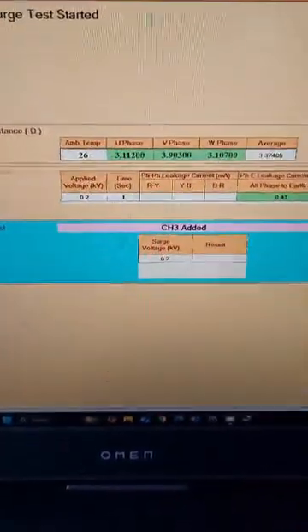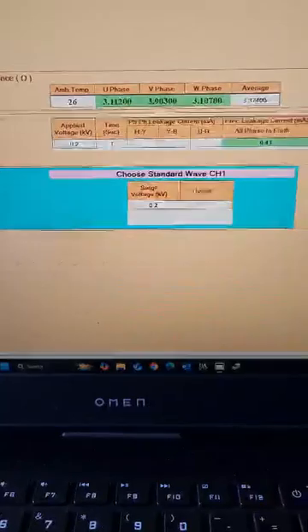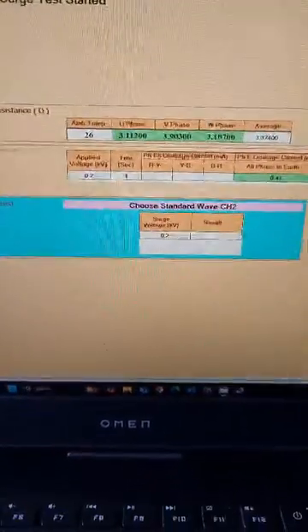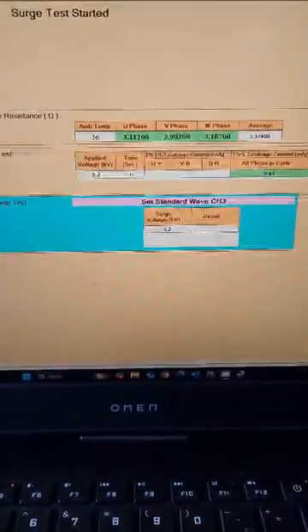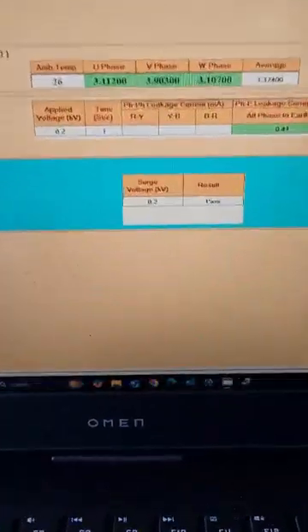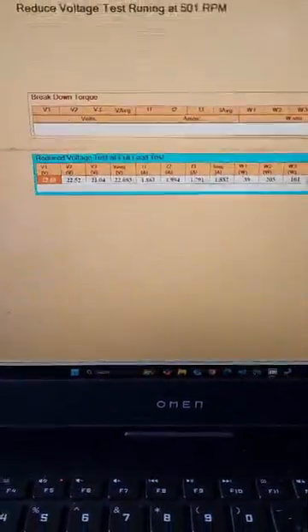And the meter that we have for the surge testing, whatever message is displayed on that particular screen of the meter is also captured on this particular testing screen of the computer, and the same thing you can see getting shown over here. Now we have completed the winding resistance test, the HV test, surge test is currently going on, and the result is shown as pass.